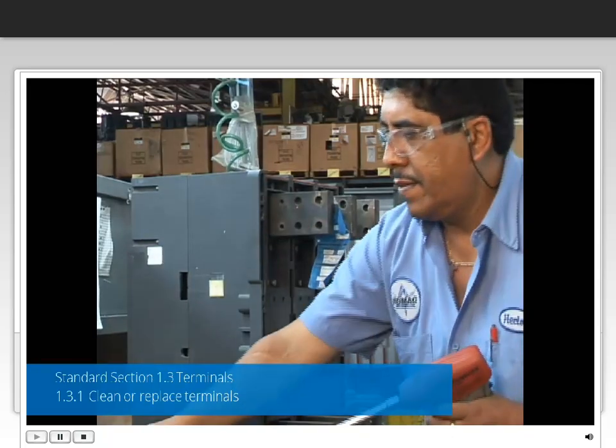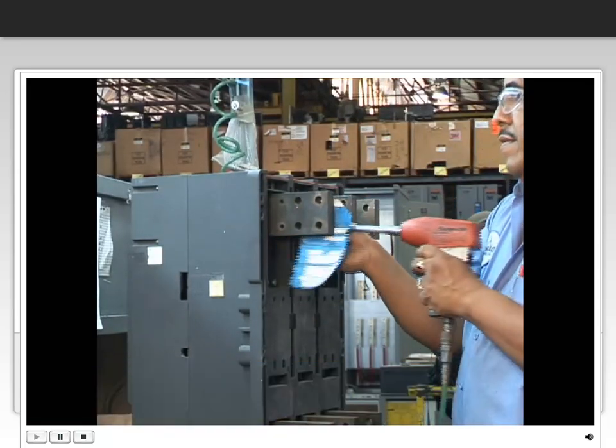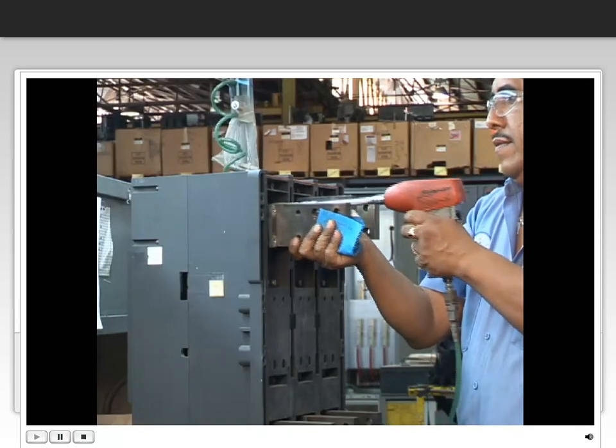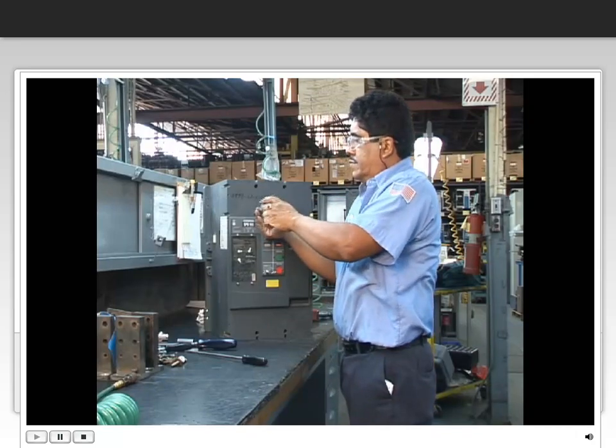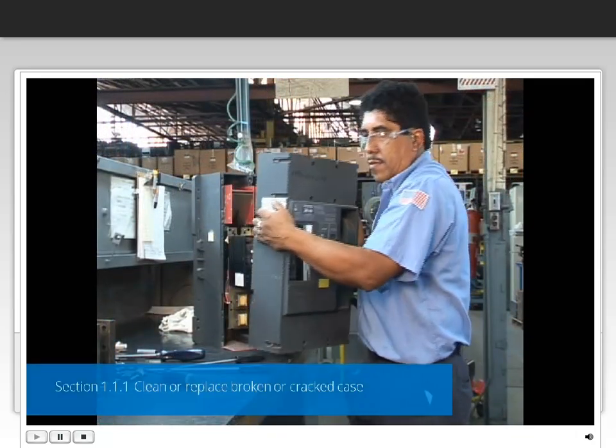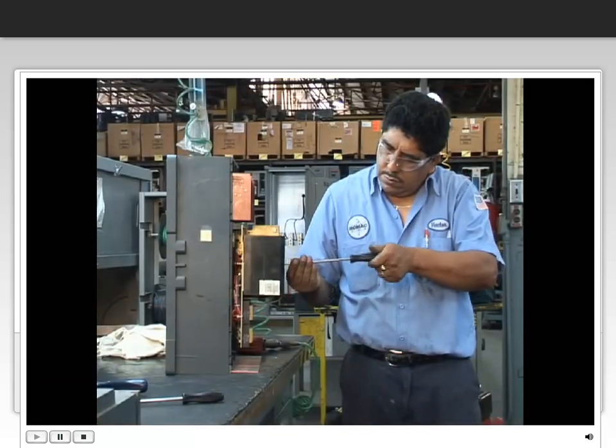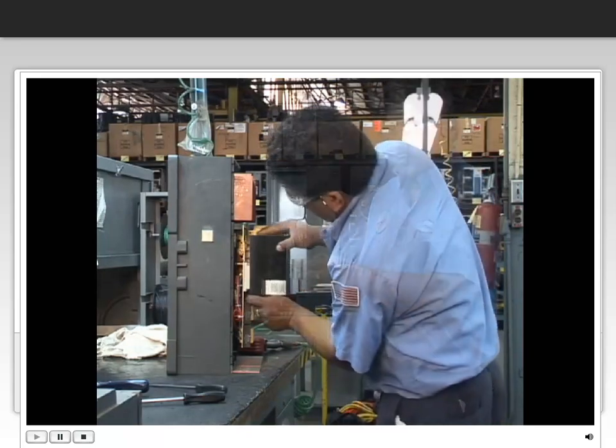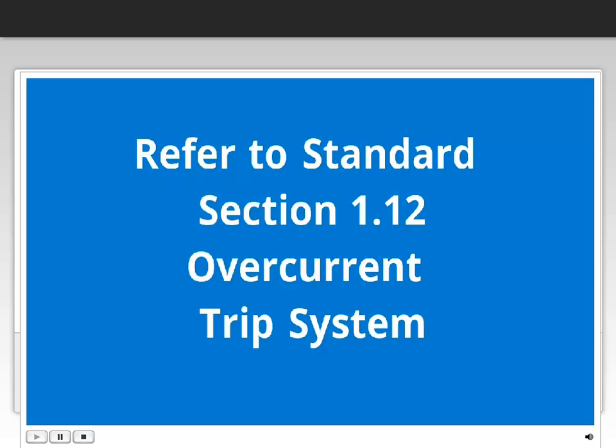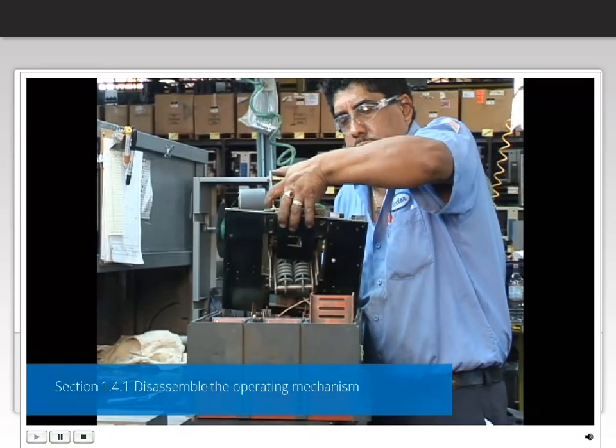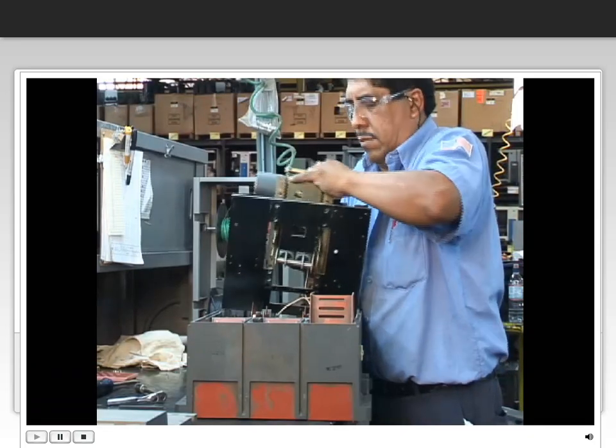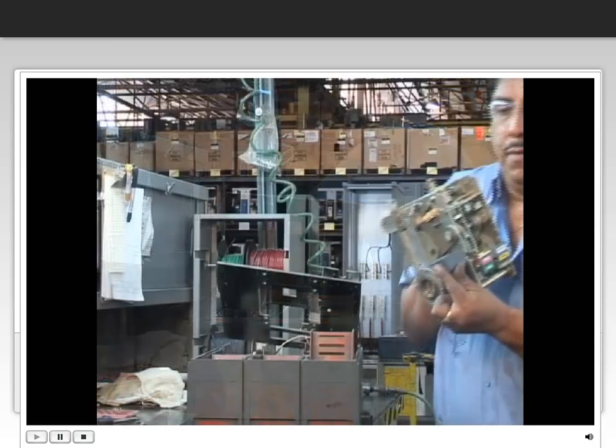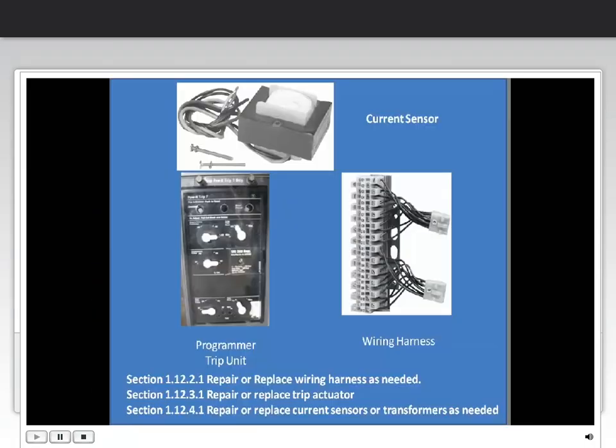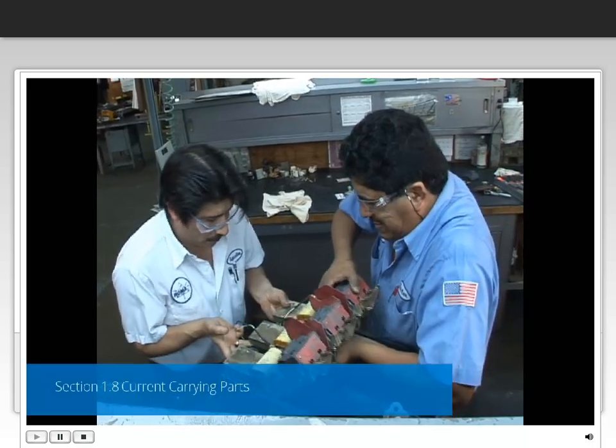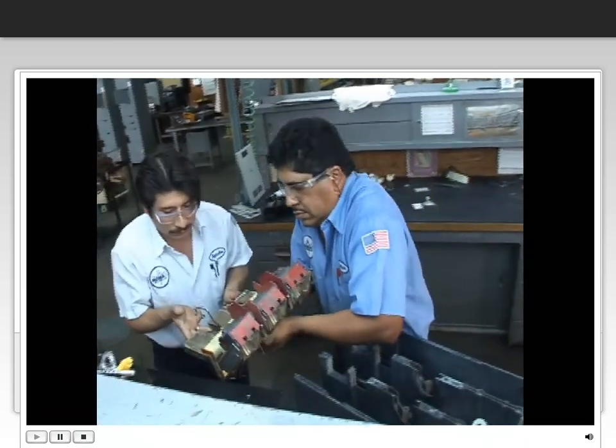First, the T-connectors are removed. After that, the trip unit cover and the breaker cover are carefully removed, making sure to check for broken or cracked covers and cases. Then the trip unit is removed. Be certain that before replacing the trip unit, it is repaired, replaced, or tested per the standard. The pawl and ratchet assembly are removed. The current sensors and wiring harness are now removed. After this, the main moving contact assembly is removed, followed by the main stationary contacts.